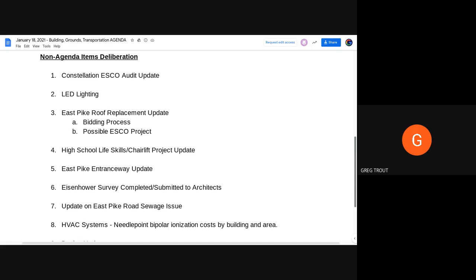Well, not to raise it, it would have to be replaced. More than likely, the suggestion was if you go to lift those units, given the age, lifting them and raising the ductwork, you'd have to actually replace all the ductwork because of the age, and more than likely the units too. That was part of what he was explaining to the contractors up there, because with any additional snow, after you raise the insulation that much, your curbs, not only for your rooftops, would be in danger of snow melting, blowing, or coming in through the units if they weren't raised, if they were maintained at the same level. That was the reason they needed to be raised.